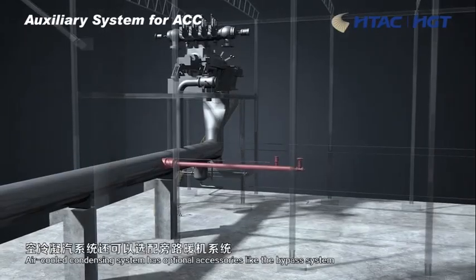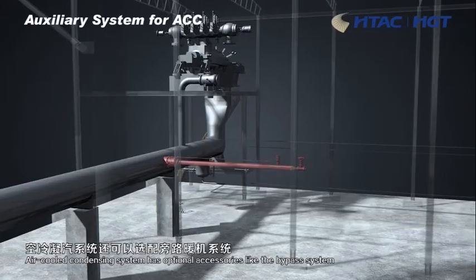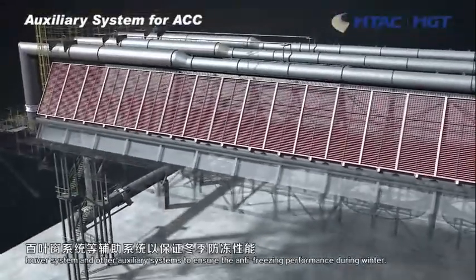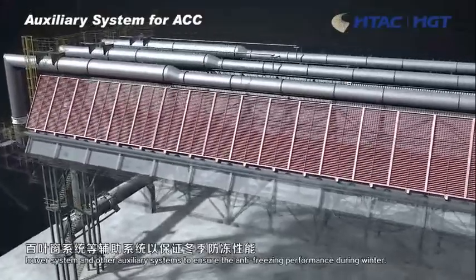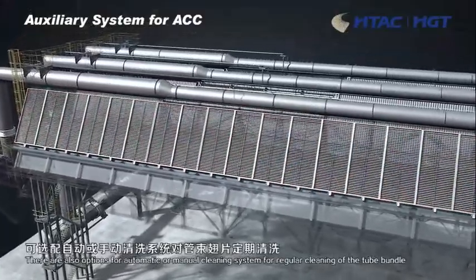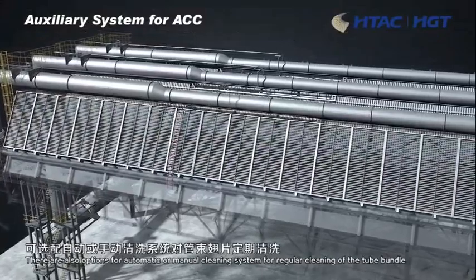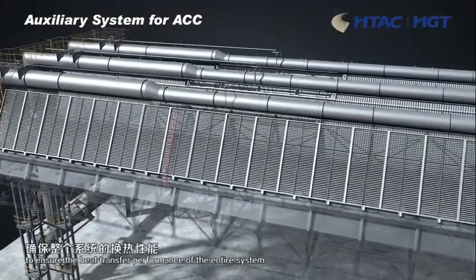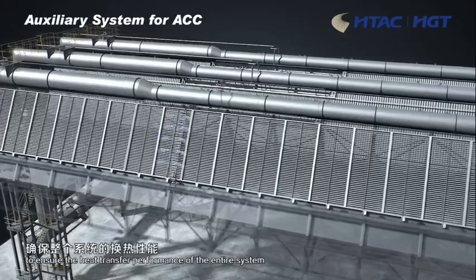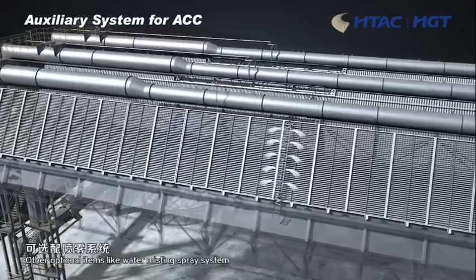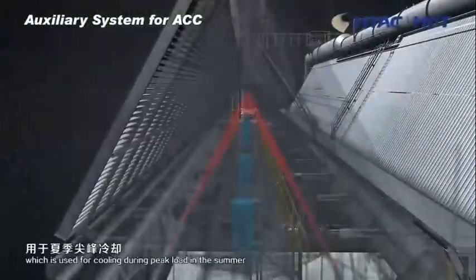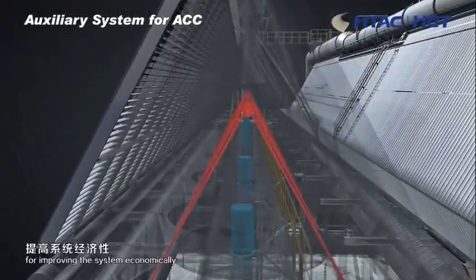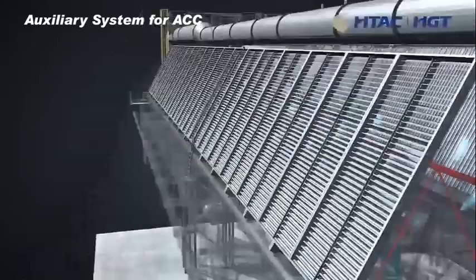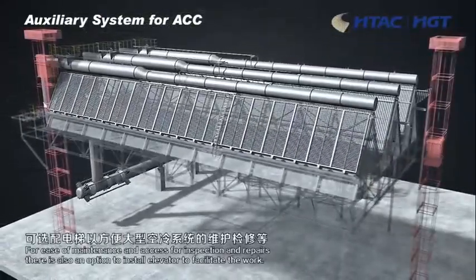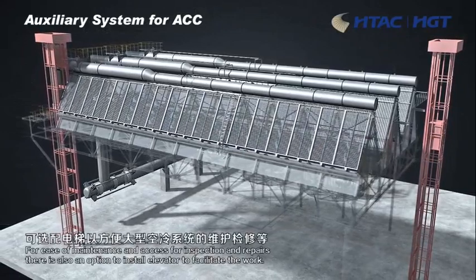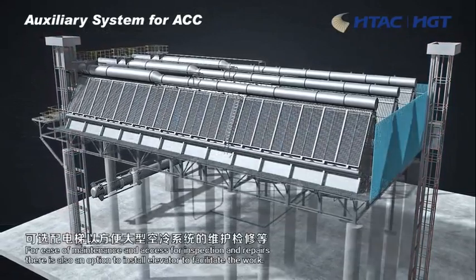Air-cooled condensing system has optional accessories like the bypass system, louver system, and other auxiliary systems to ensure the anti-freezing performance during winter. There are also options for automatic or manual clean system for regular cleaning of the tube bundle to ensure the heat transfer performance of the entire system. Other optional items like water misting spray system, which is used for cooling during peak load in the summer for improving the system economy. For maintenance and access for inspection and repairs, there is also an option to install an elevator to facilitate the work.